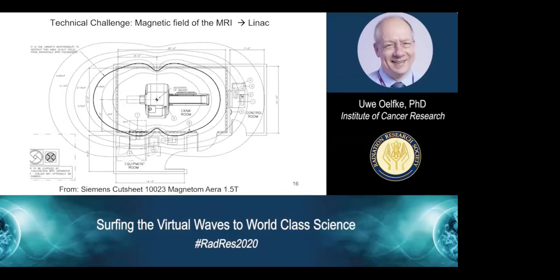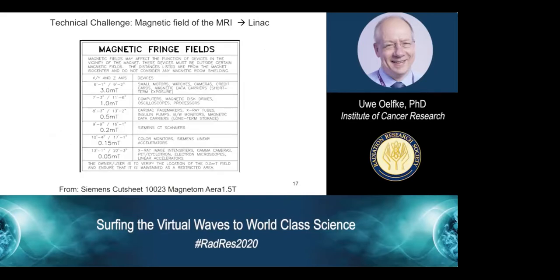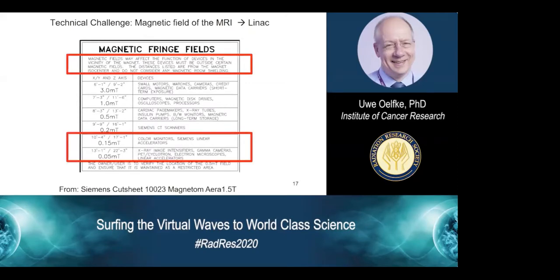Let's first discuss the challenge that the magnetic field of the MRI scanner poses on the operation of the LINAC. Here you see the distribution of magnetic field lines in the room of a 1.5 Tesla MRI, and the thick black line indicates the 0.5 millitesla field strength. If you look in the handbook of the MRI scanner, you already find a warning that the operation of certain electrical devices in this magnetic field is not allowed or should not be done. Magnetic fields may affect the function of devices in the vicinity of this magnet, and specifically linear accelerators, X-ray image intensifiers, and gamma cameras get a warning that one should not do this.